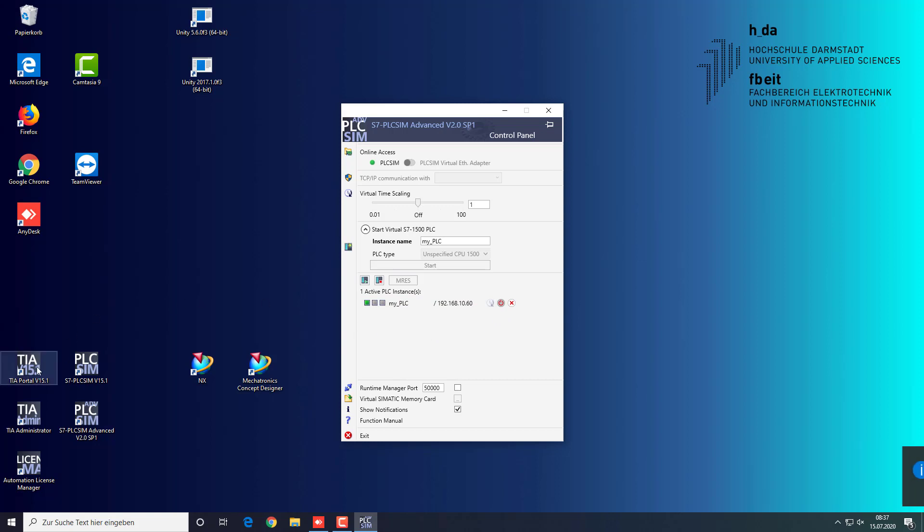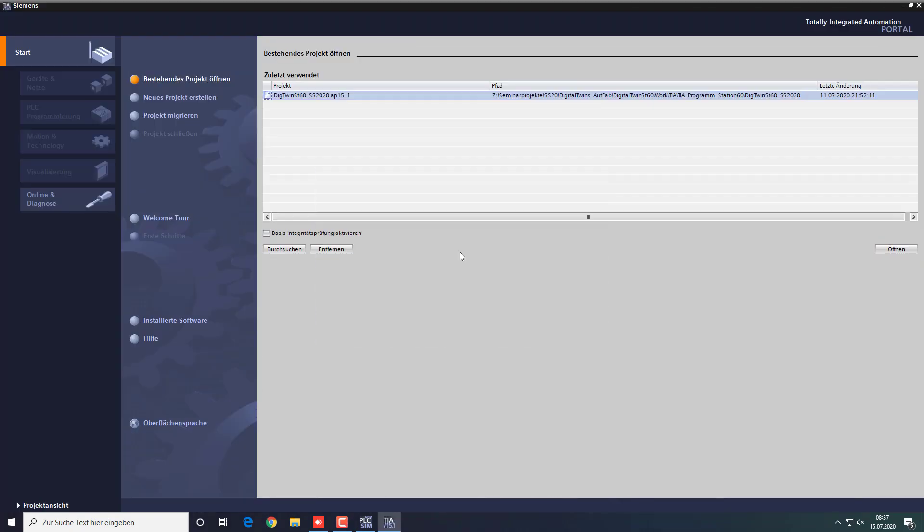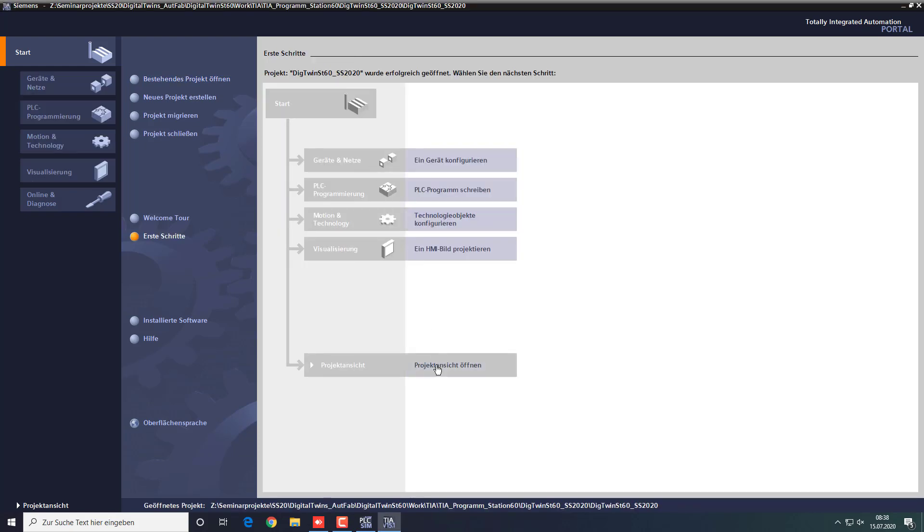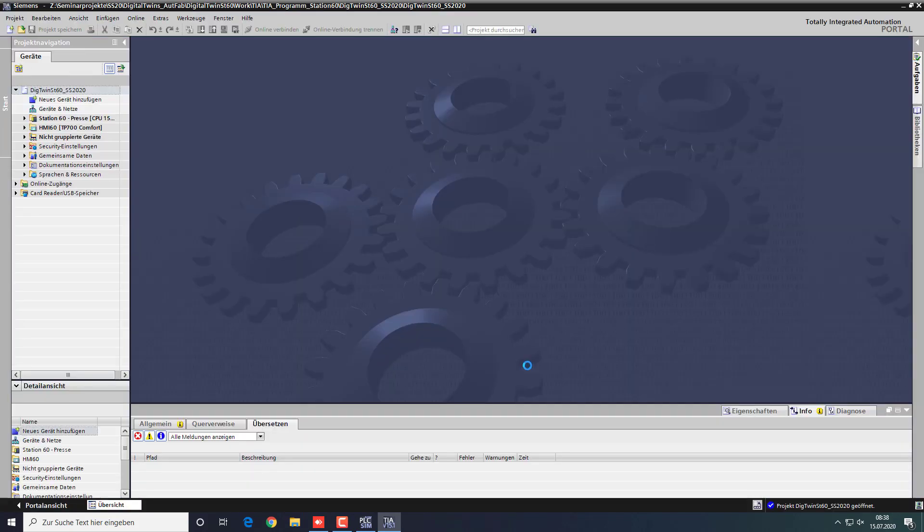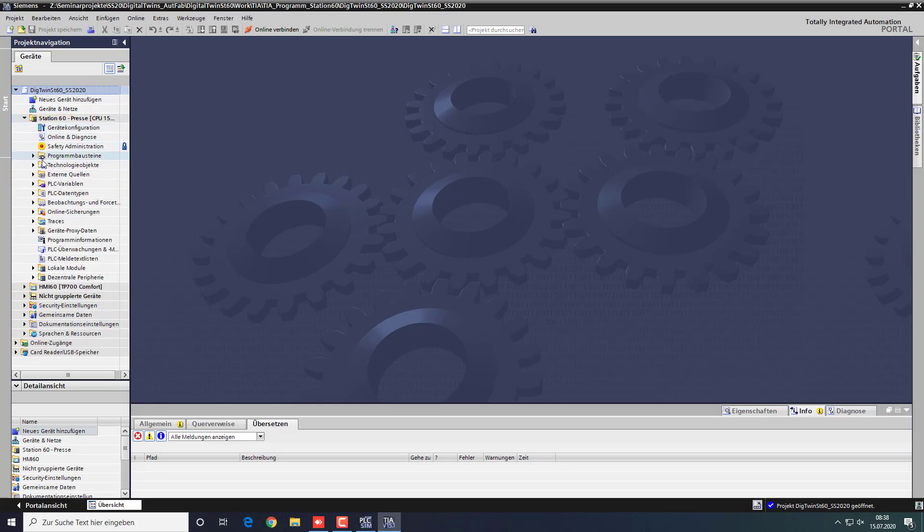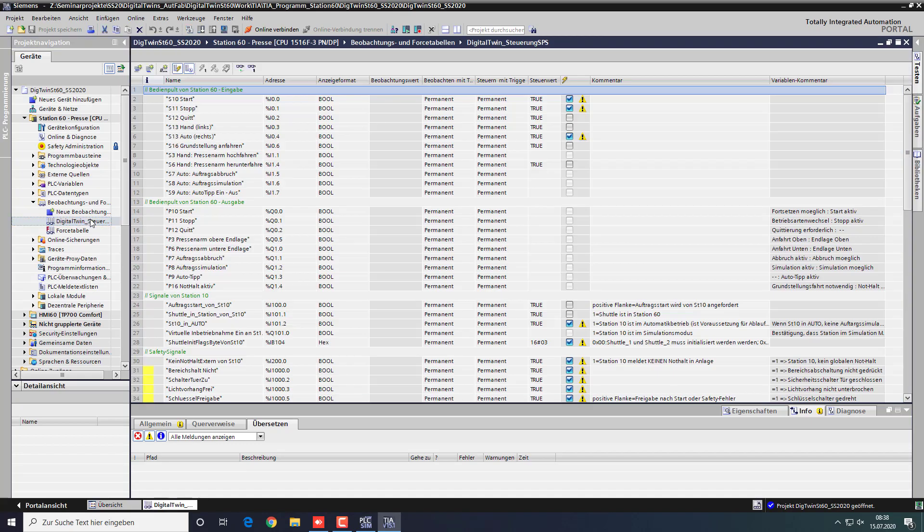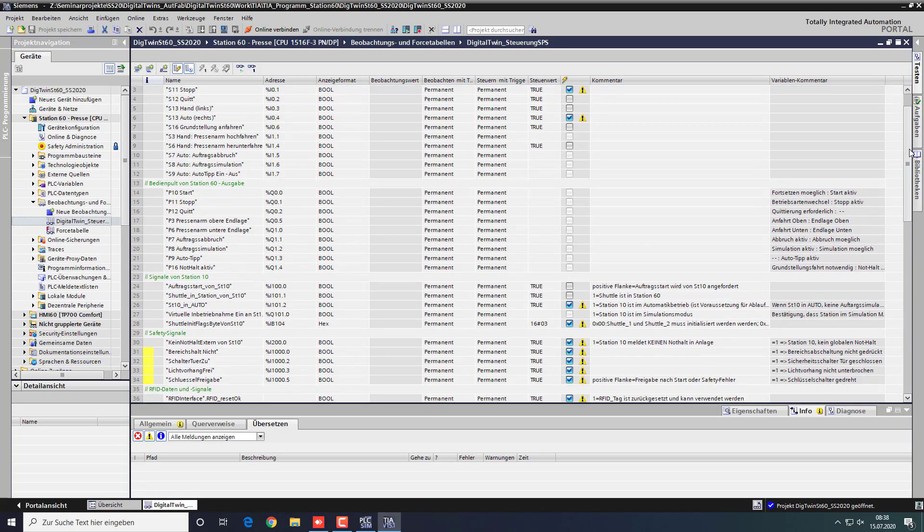Now you start the TIA portal and open up your project. This project is the one running on your PLC. You navigate to the watch tables. Ours has already been created and set up. The watch table is used to provide the PLC with the necessary input signals that the digital twin cannot provide.